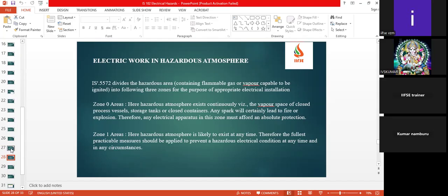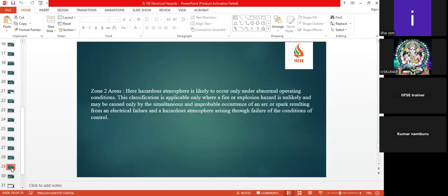Then zone 1. Here the hazardous atmosphere is likely to exist at any time. Therefore, the fullest practical measures should be applied to prevent a hazardous electrical condition at any time and in any circumstances. So this is a kind of zone where the atmosphere can occur at any time. Previously it was continuously present, but in zone 1 it can happen anytime. So all our electrical appliances should be ready for such situations. They should not generate any spark or any heat.